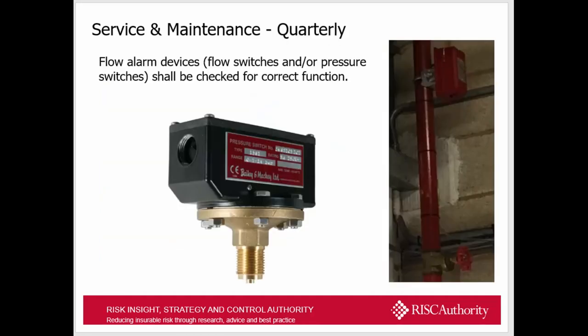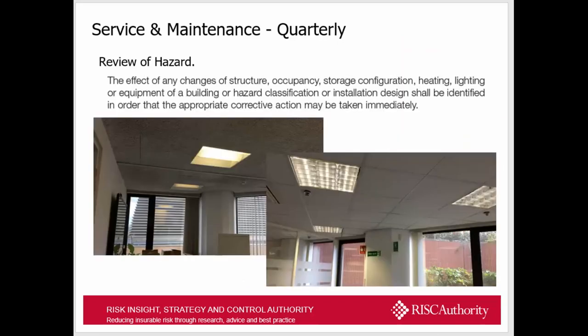Moving on to quarterly requirements. These service activities must be undertaken by a third-party approved and accredited service provider, listed within their scope of certification. There are three approval schemes available: LPS 1048 run by the LPCB, which is part of BRE; the FIRAS scheme by Warrington Fire; or the IFC, International Fire Consultants. These schemes provide certification for service contractors for third-party approval. On a quarterly basis, all flow alarm devices shall be checked for correct function — every 13 weeks, flow switches and pressure switches shall be tested.